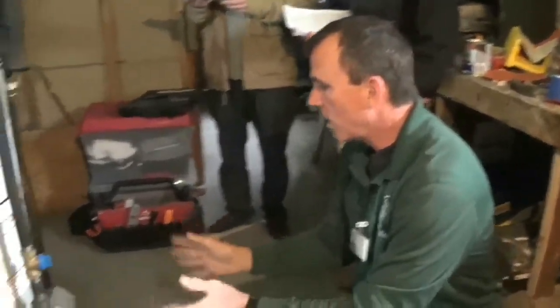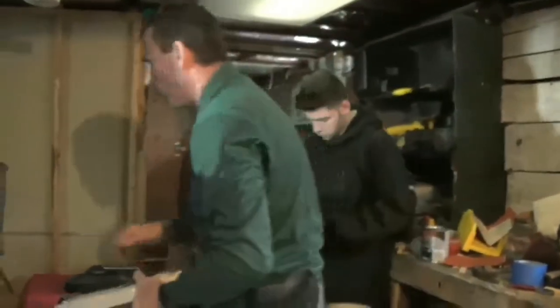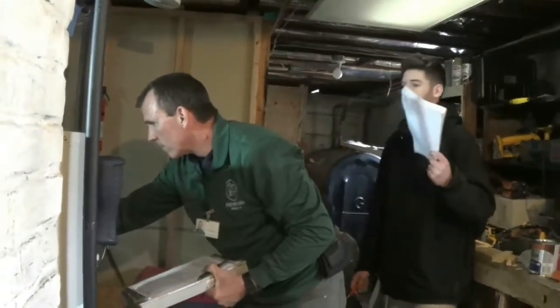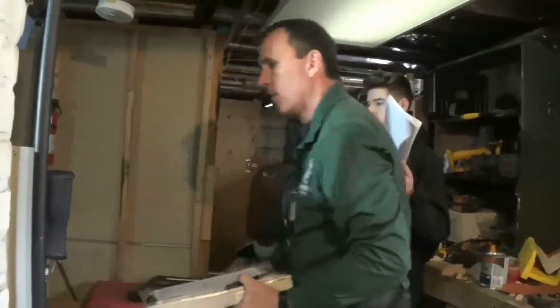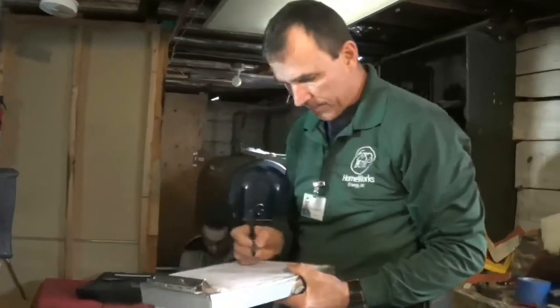So we've had all our equipment running for some time now, and I now have my Bacharach probe laying on the floor to cool it off, and I'm also getting the ambient in the air, and it's down to 0. It went down to 0 almost right away. So that's good. That's a number we also have to write down on our sheet. For the combustion appliance zone, the ambient is 0. All right. I'm going to turn the boiler back off again. And it's still at 0, so that's great.